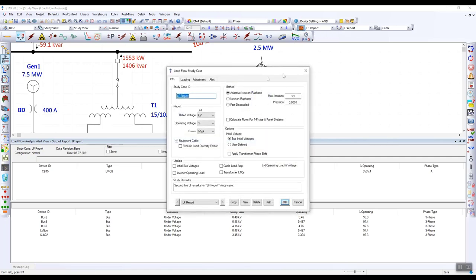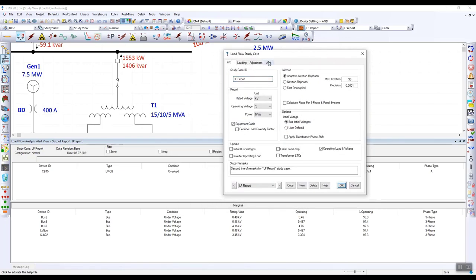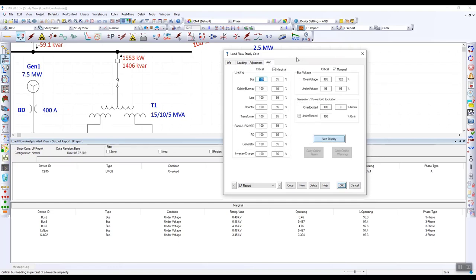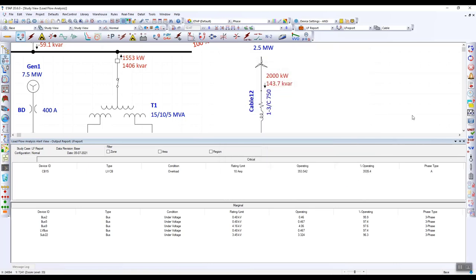These alerts are based on percent thresholds that you have set in the load flow study case. Any device that exceeds 100% loading will generate a critical error, and anything between 95 and 100% will generate a marginal error. To the right, we have thresholds for our buses and over and under excited thresholds for our generators and utilities. You could also create various scenarios using our multi-dimensional database where you can change the rating for existing devices.